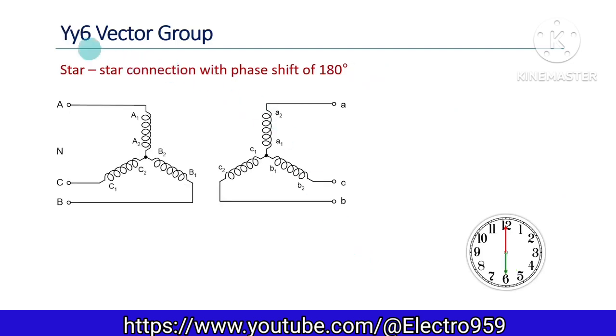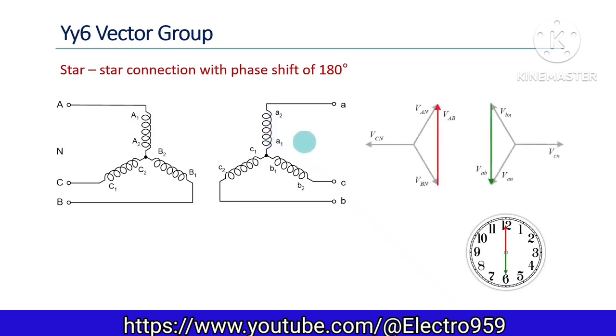Next up is the YY6 group. Both the primary and secondary windings are star connected, but the polarity of each winding is reversed on the secondary side. On the primary side it is A1, A2, and on the secondary side it is A2, A1. This reversal of polarity is done in all other windings as well. This results in a 180-degree phase shift in the secondary voltages, represented by the clock hand position at 6 o'clock. The simplified connection diagram and displacement diagram are shown accordingly.